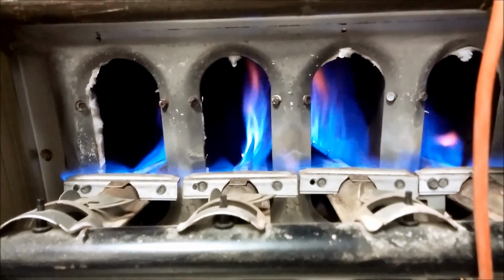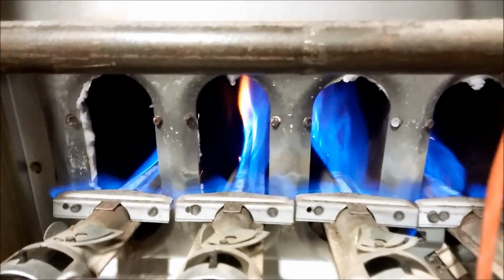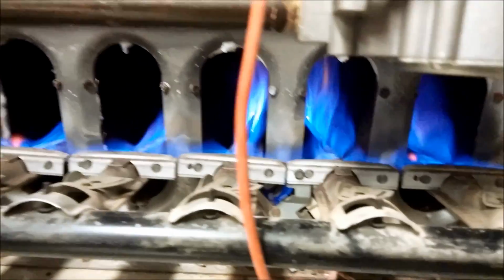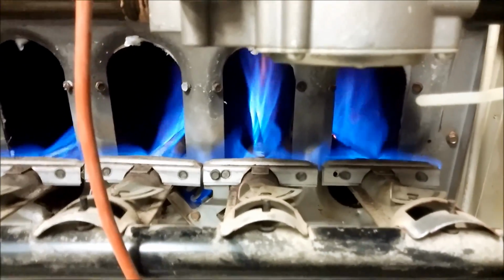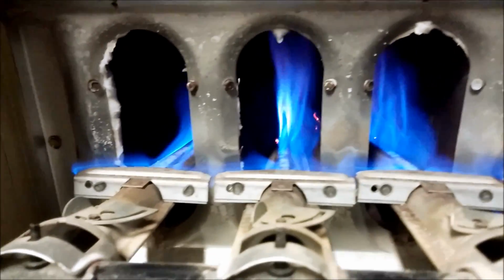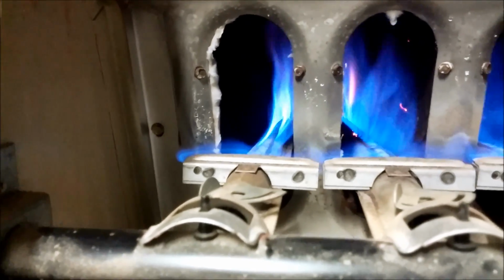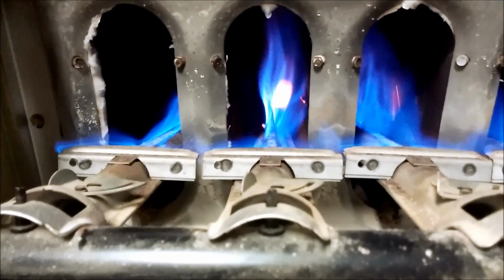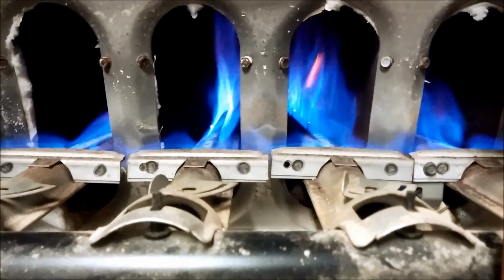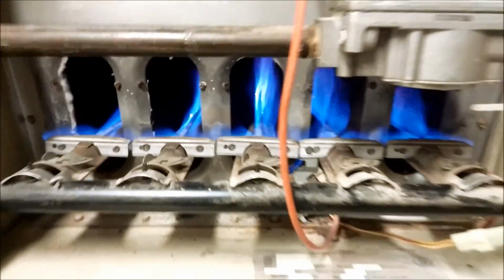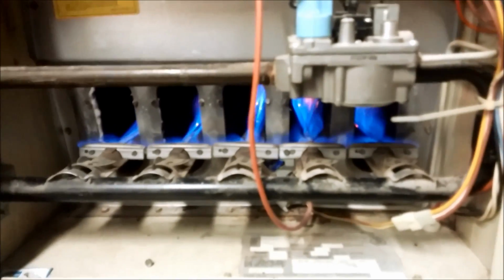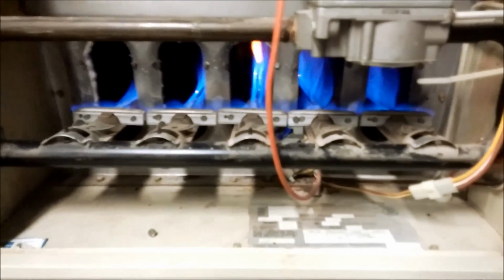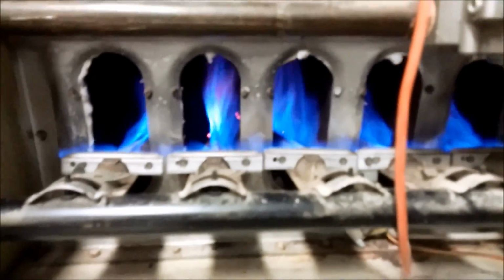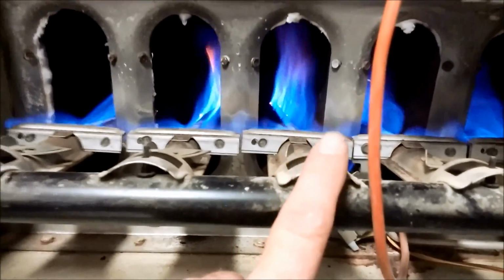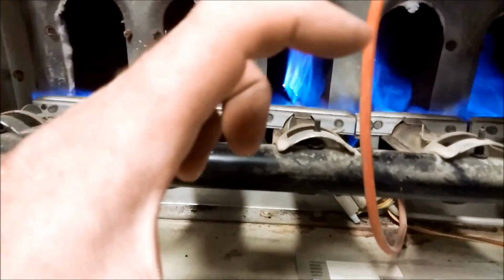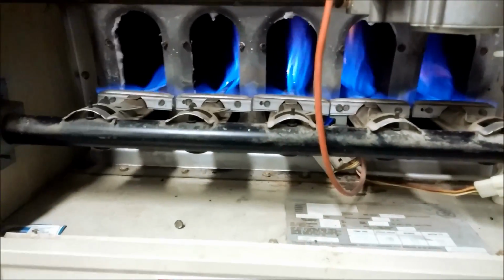Gosh, I got gaping holes in there. Gaping holes in that heat exchanger. See any flame roll out? Absolutely nothing. So if you're telling me you can't find a cracked heat exchanger because it doesn't have flame rollout, that's the reason why. You're not looking. Gaping holes, especially in this one, wide open. I have a wide open crack about 6 inches long.